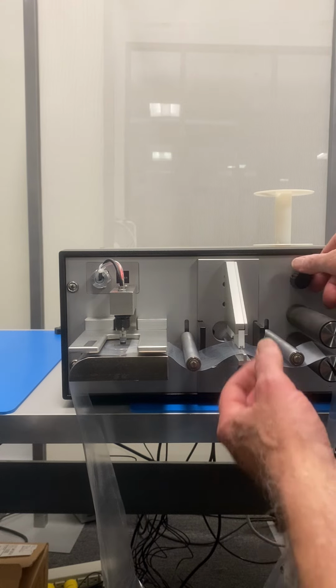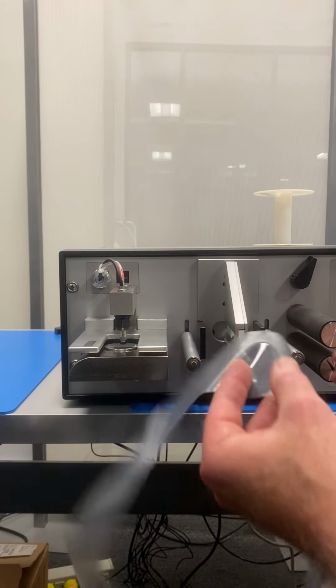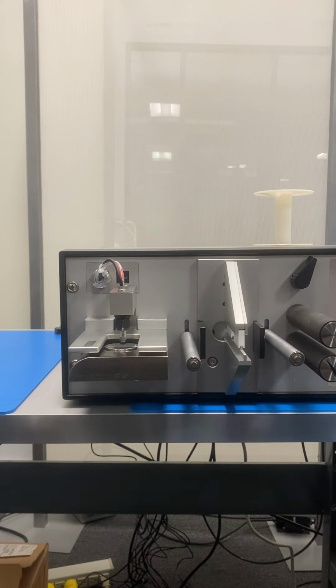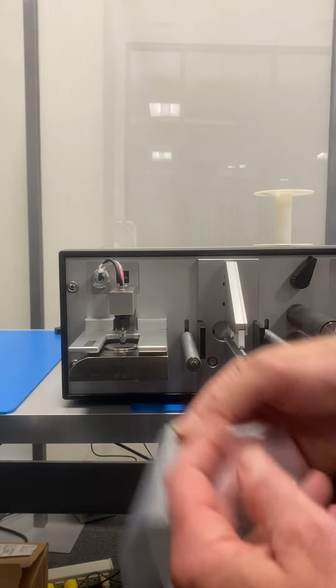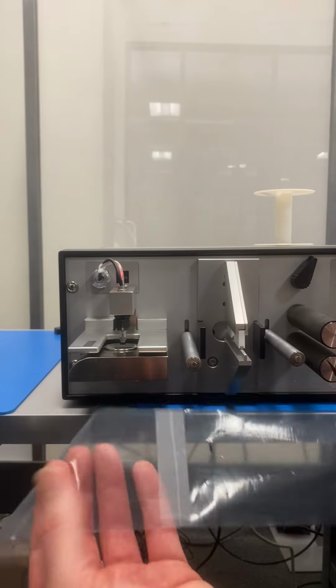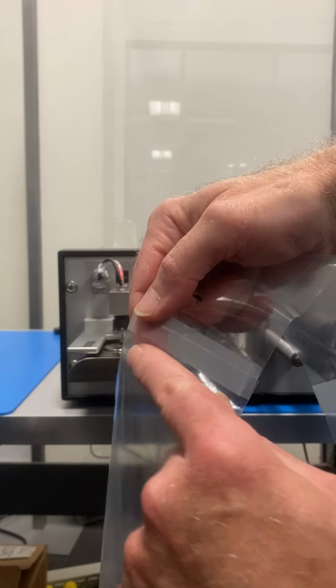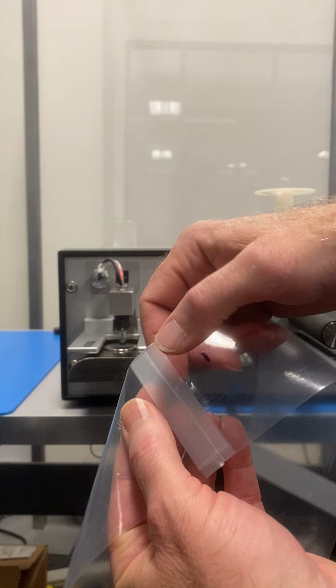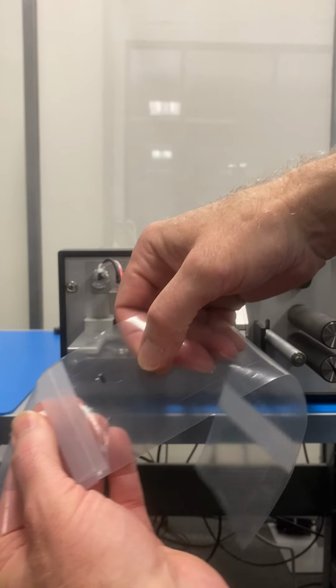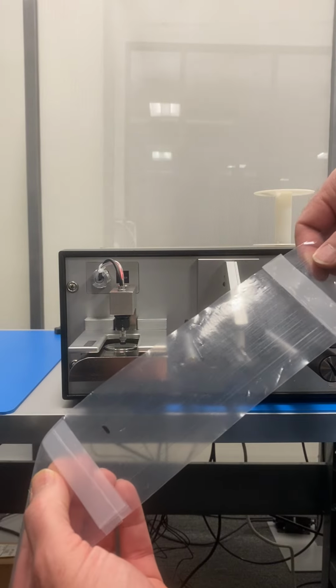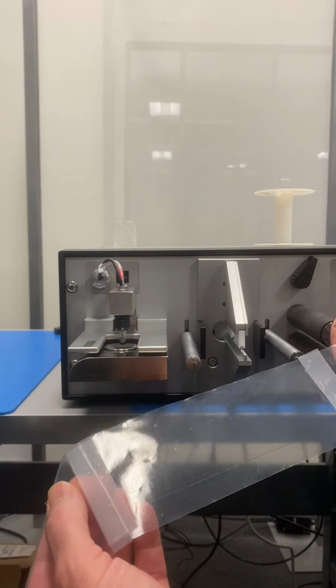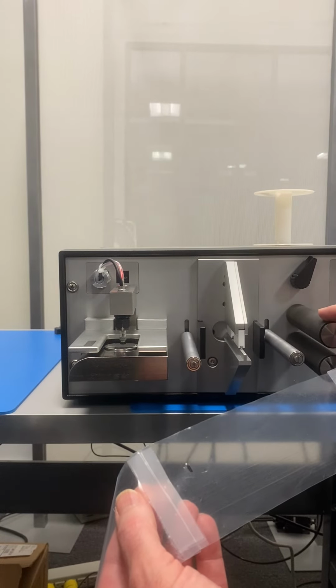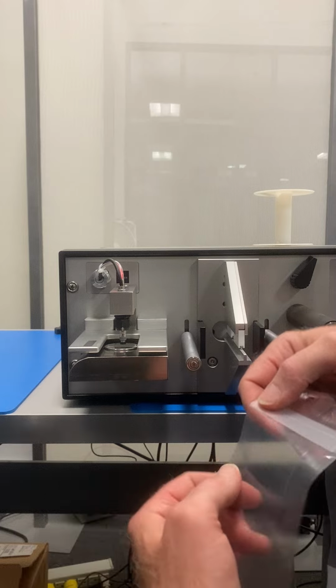A second method, should you choose to run in a strip format rather than taping it together in a tube, I prepared one by just cutting the tube that I demonstrated. Let's say that this is the beginning part of your sample. We'd recommend that you tape a leader from the beginning of the sample of film or paper that is at least long enough to run underneath the drive so that you can pull your sample through the contact probe.